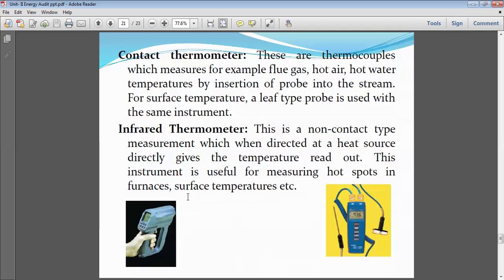Therefore we use infrared thermometers for high-temperature cases. Contact thermometers are used in silos — in process, chemical, or pharmaceutical industries, stainless steel containers are connected by pumps to transfer fluid, and RTD-type or thermocouple-type thermometers are permanently installed on the silos or containers to indicate the temperature of the system, containers, or fluids such as liquids, gases, and water.